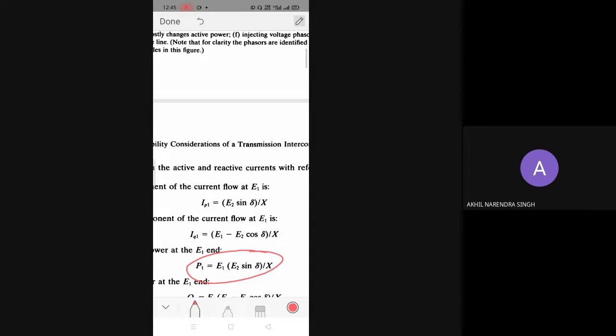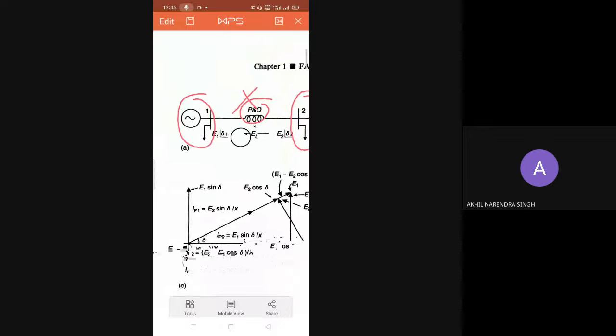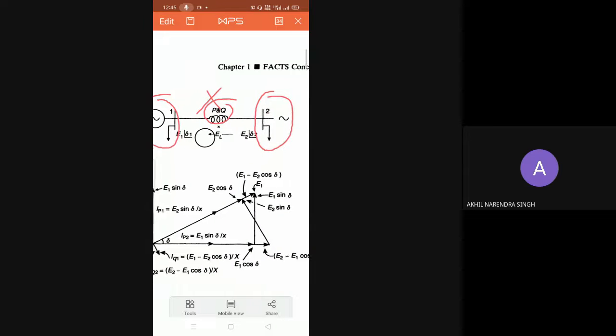So here, P1 means the power which is injected by region 1 into the transmission line. P1 is the power which gets injected by region 1 into the transmission line. Now if we talk about the transmission line, only the inductive reactance is considered. So there is no real power loss in the transmission line. Because of that, whatever power is injected by region 1 into the transmission line, the same power will be drawn by region 2 from the transmission line.